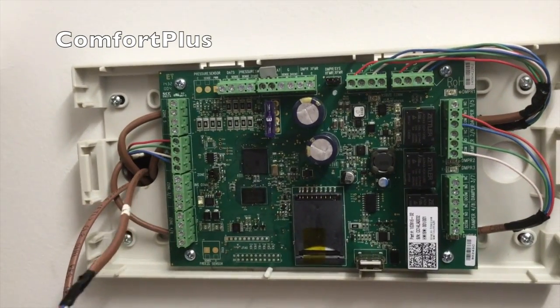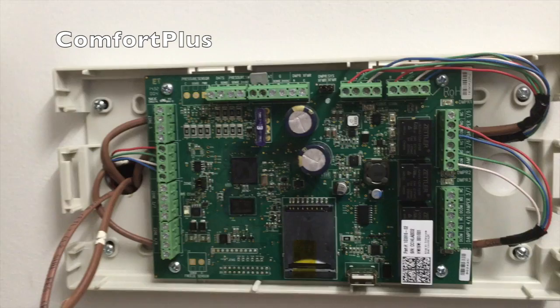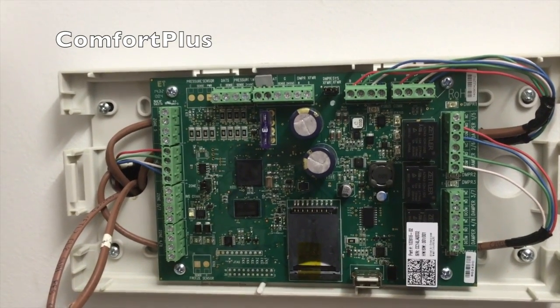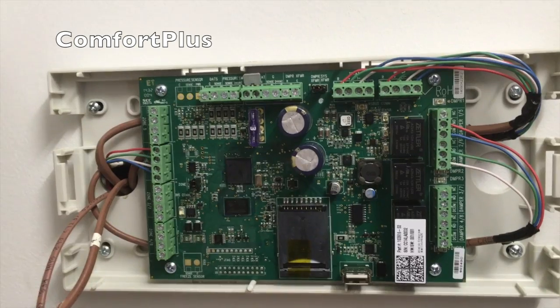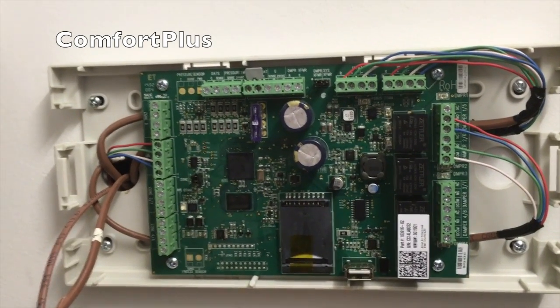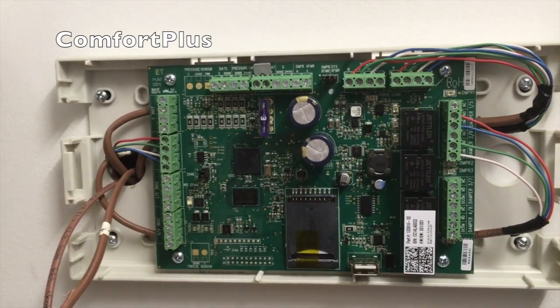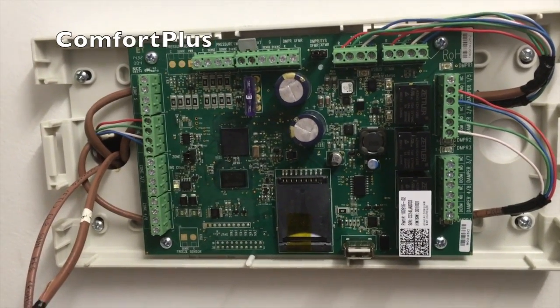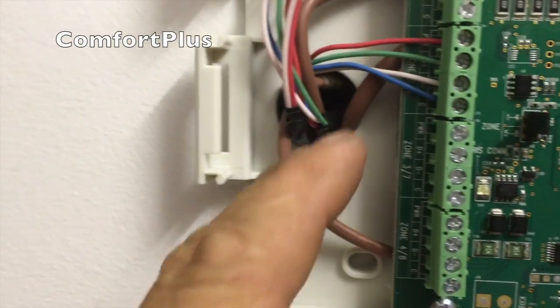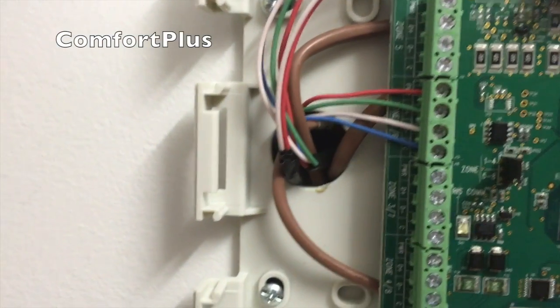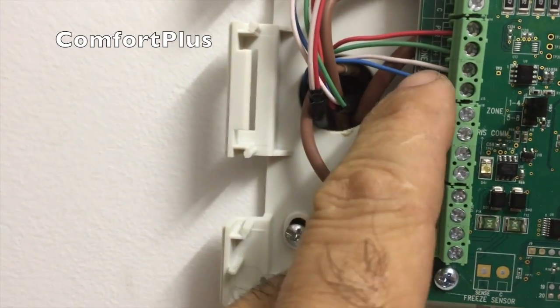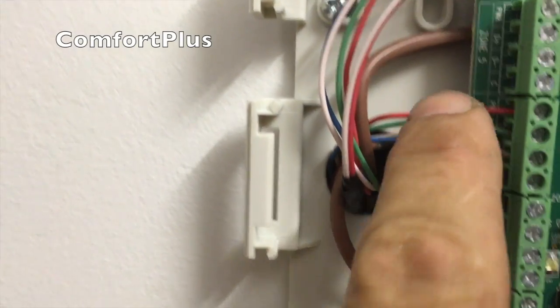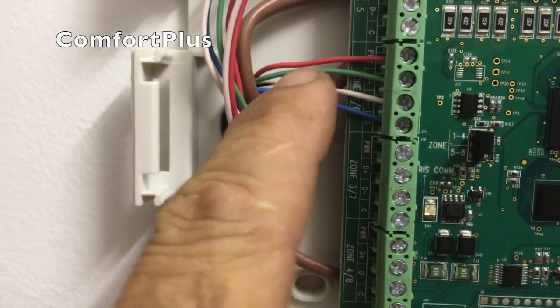So make a couple more connections here, and then I can put the zone sensor in the actual ComfortSync thermostat, about the size of a small iPad. I can hook it up and have everything ready to go. Okay, so over on the left side here is where you hook up your zone sensors. Since I only have 2 zones, I'm only using one of these terminals, and it's the regular 4-wire bus. The 2-wire connector I got here is for my discharge air temperature sensor. Goes on those 2 screws.